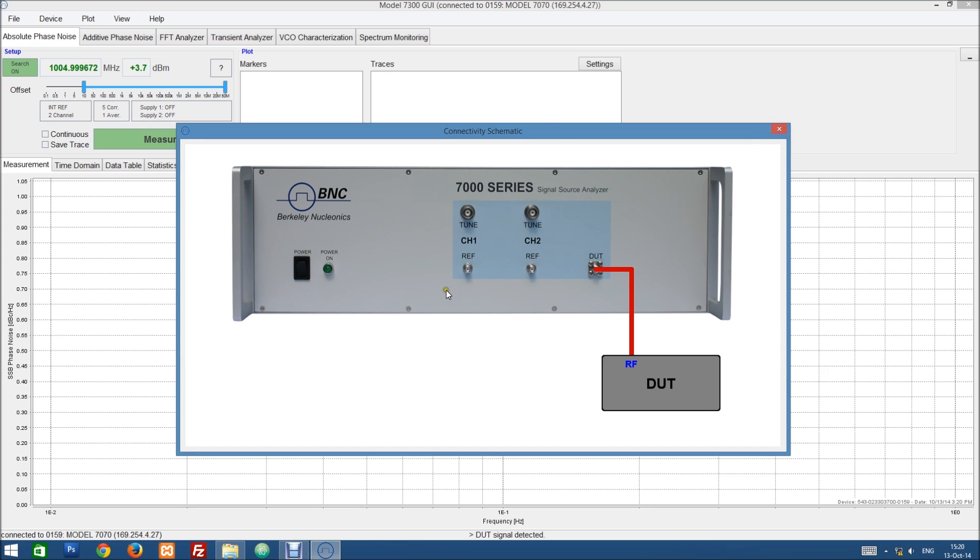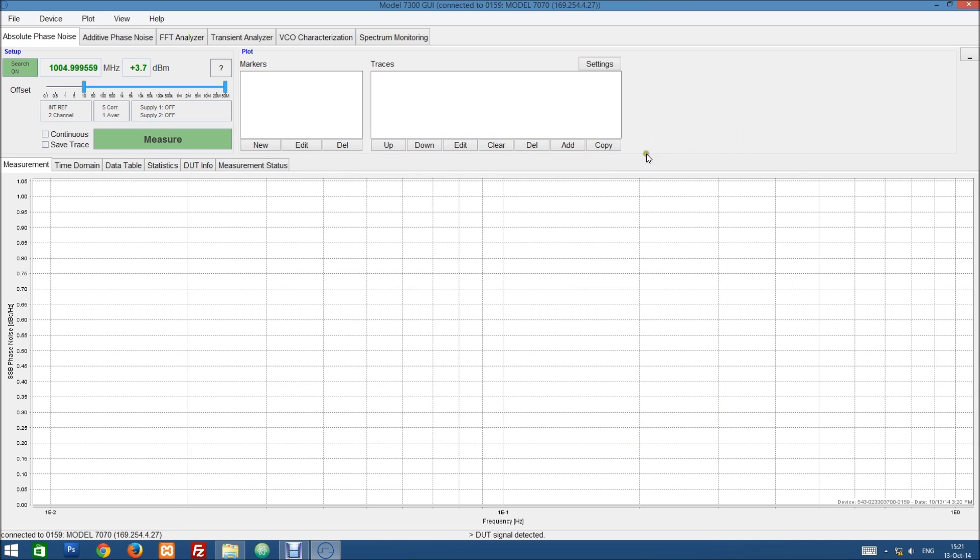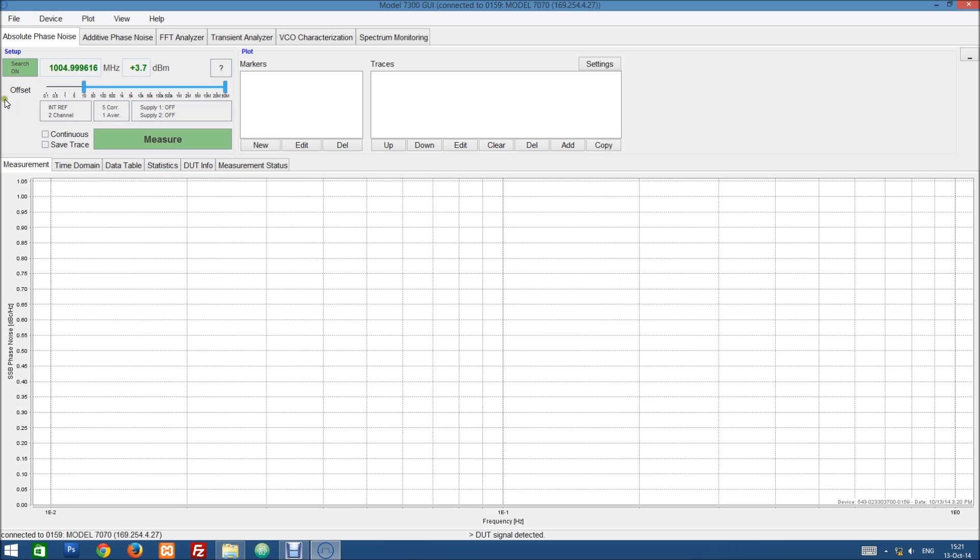But if you use external references or do an additive phase noise measurement, this setup might be a little bit more complicated and the schematic can be quite helpful. So on the second line we can choose the frequency offset of our measurement. So let's choose a measurement of 10 hertz to 50 megahertz.